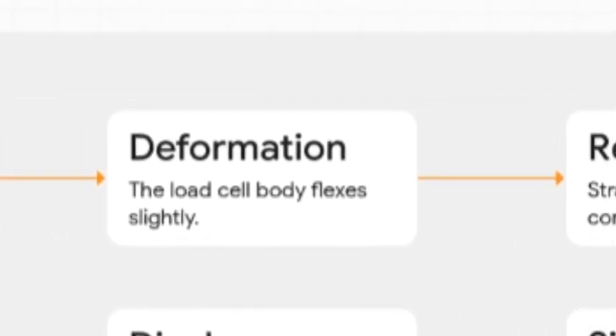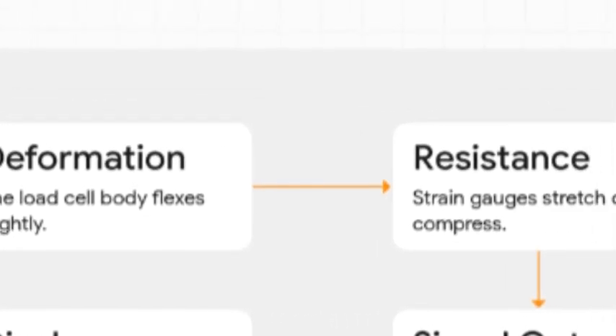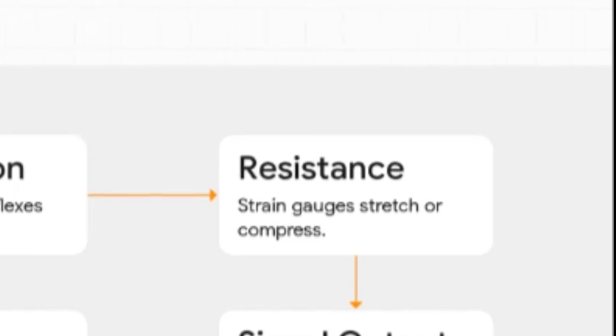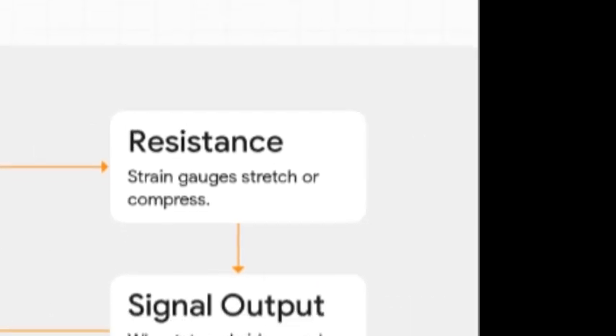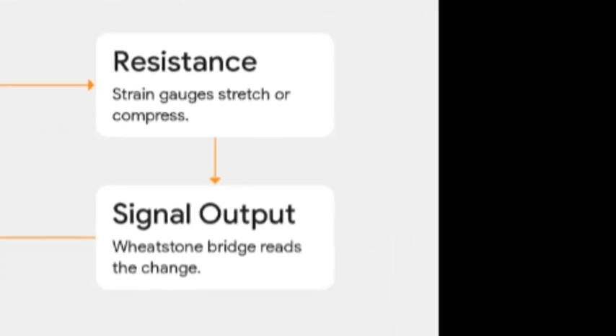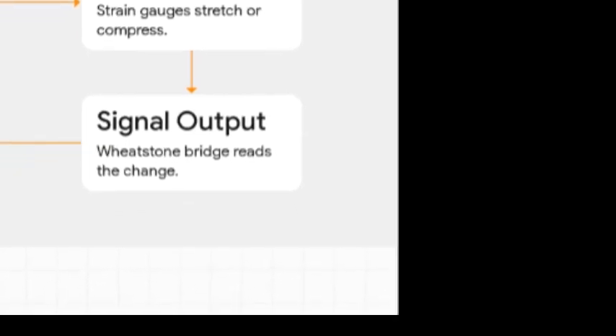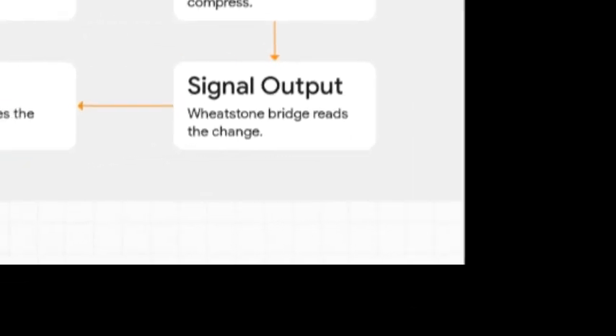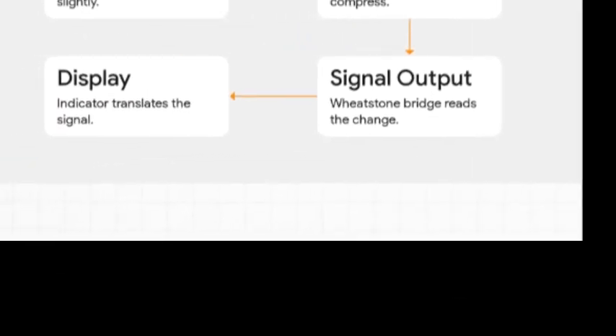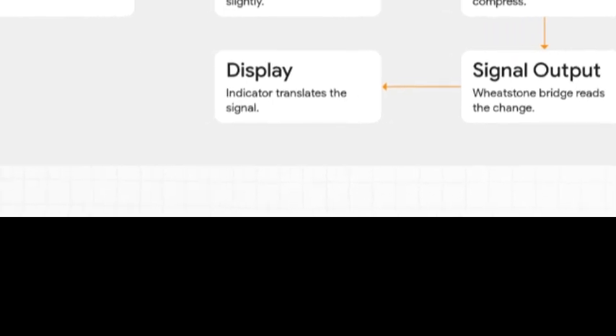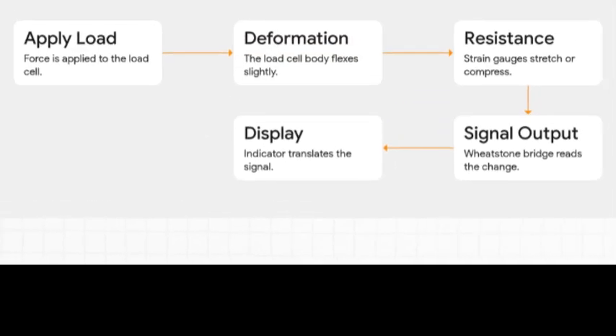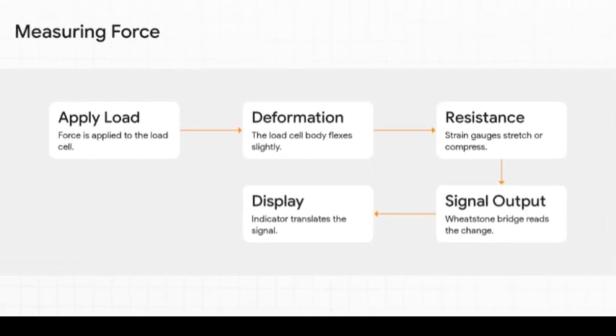Step 2, the solid metal body elastically bends. You can't see this with the naked eye, but it is bending. Step 3, that microscopic deformation causes the glued-on strain gauges to change their electrical resistance. Step 4, the Wheatstone bridge grabs that resistance change and outputs a clean electrical signal. Finally, Step 5, the indicator translates that signal into the kilograms or pounds that pop up on the display.